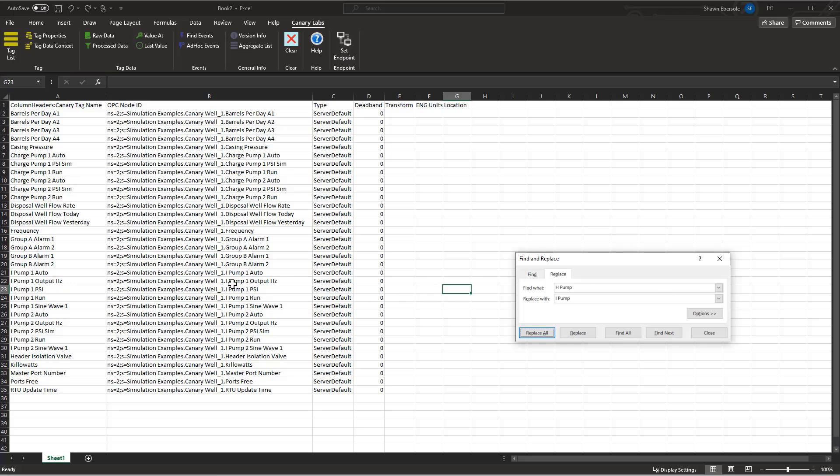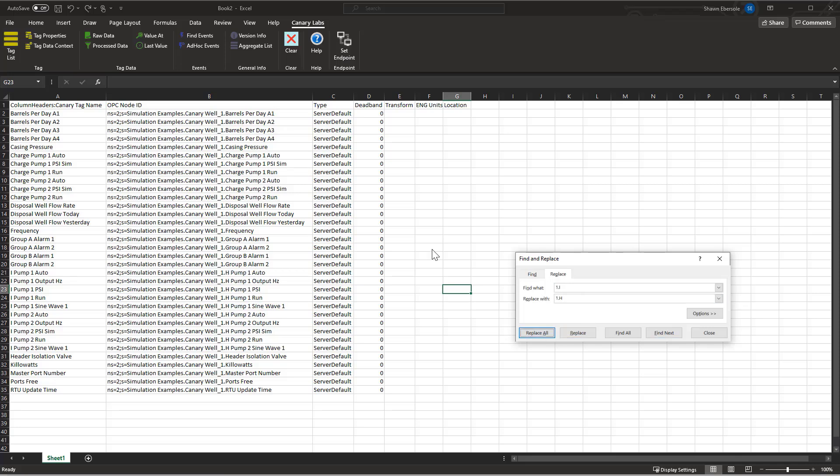Now what I did here was I updated the OPC node ID name as well, which I don't want to do that, because it's important to note that this is the actual mapping of our tag names back into the OPC server. So it's important that I don't change these. Okay, so I fixed that.